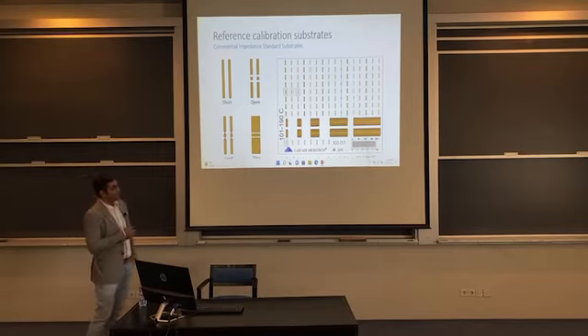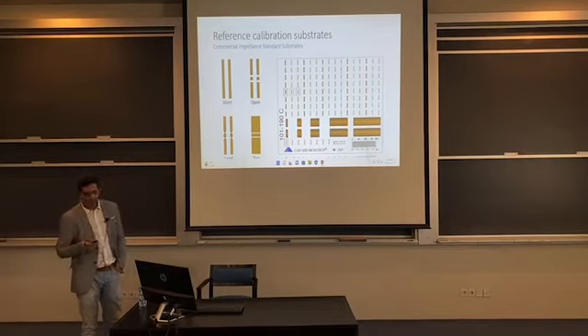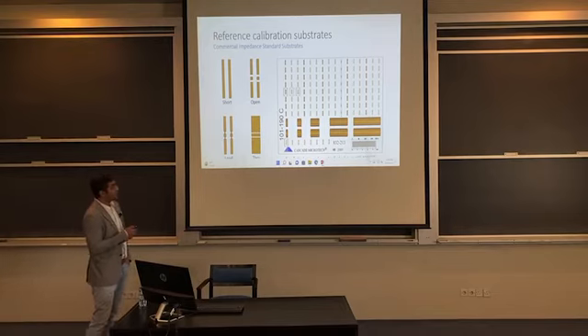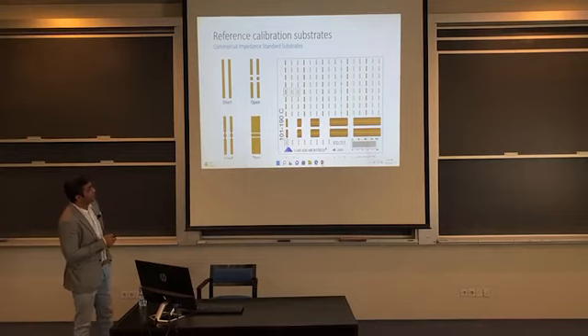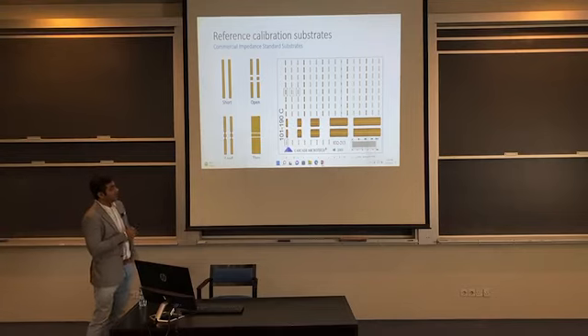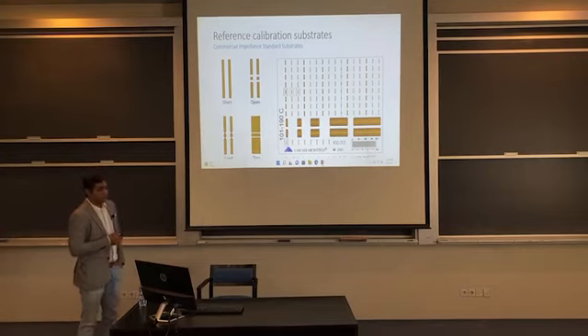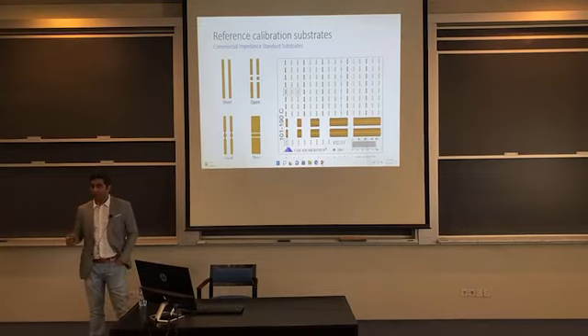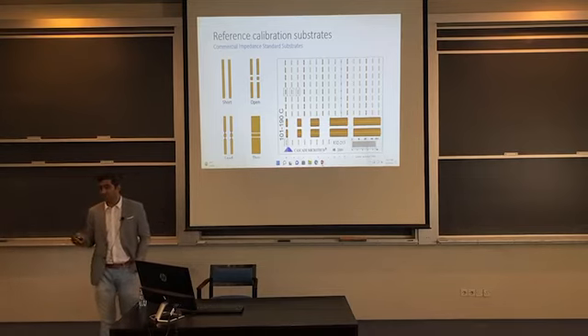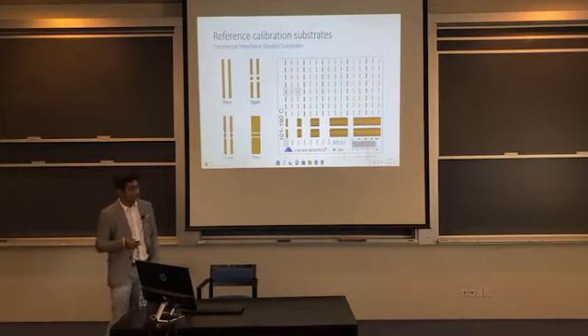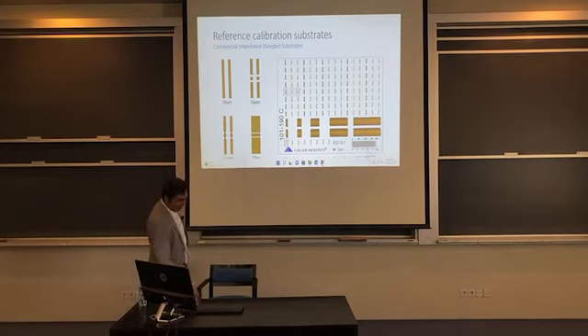Development of these reference standards is a domain in itself. You can buy commercial reference substrates like these from Cascade Microtech, which have a range of devices on them. However, the problem is these are not traceable. We don't have reference data given by the manufacturer, which basically means that for any traceable measurement that we want to do, we need to design our own reference standards.